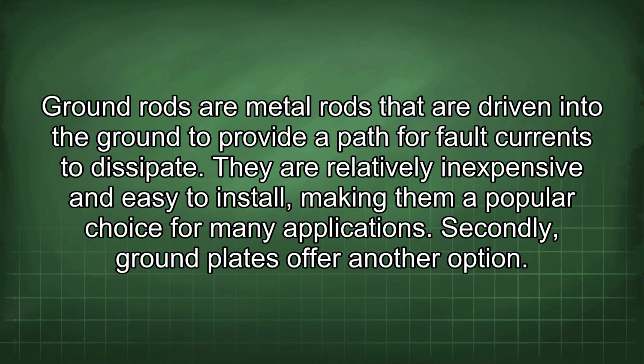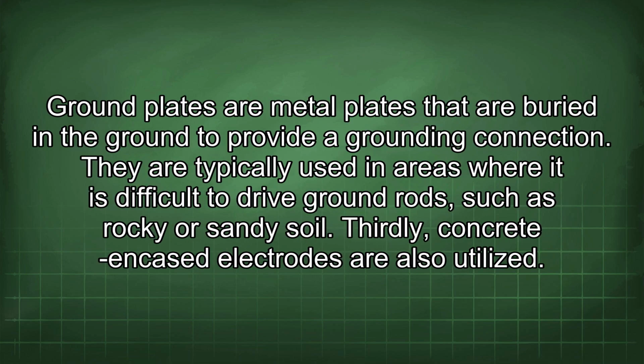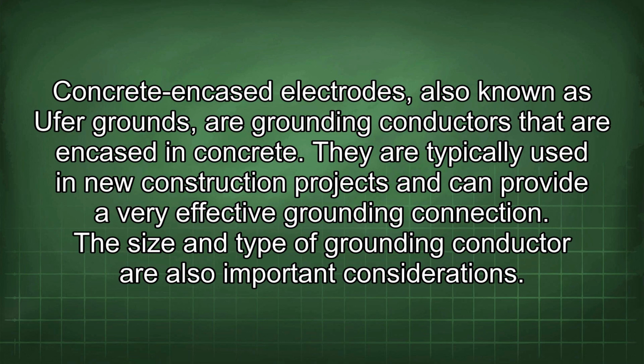Secondly, ground plates offer another option. Ground plates are metal plates that are buried in the ground to provide a grounding connection. They are typically used in areas where it is difficult to drive ground rods, such as rocky or sandy soil. Thirdly, concrete encased electrodes are also utilized. Concrete encased electrodes, also known as UFER grounds, are grounding conductors that are encased in concrete. They are typically used in new construction projects and can provide a very effective grounding connection. The size and type of grounding conductor are also important considerations.